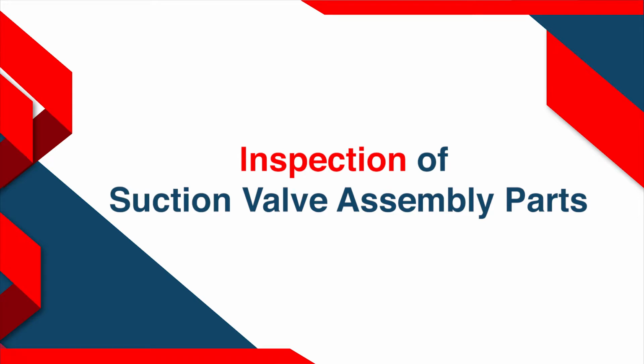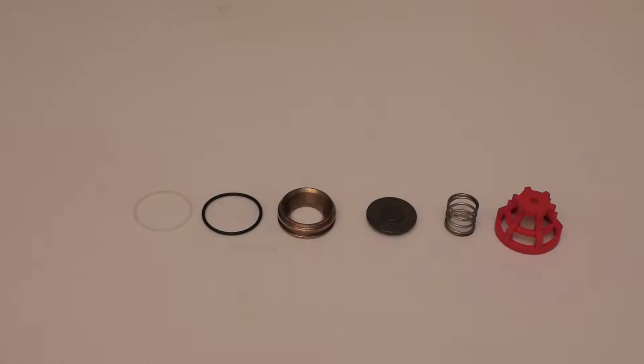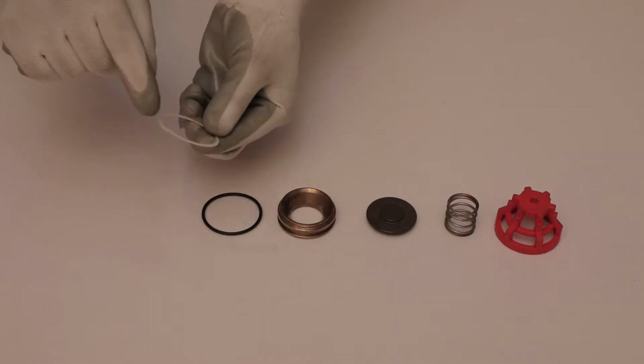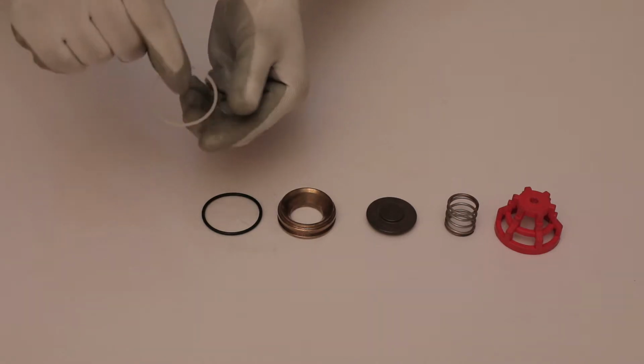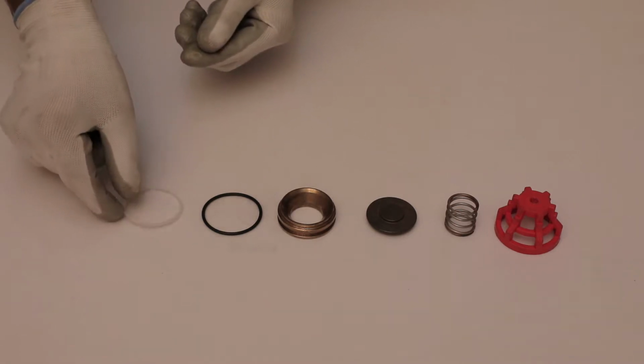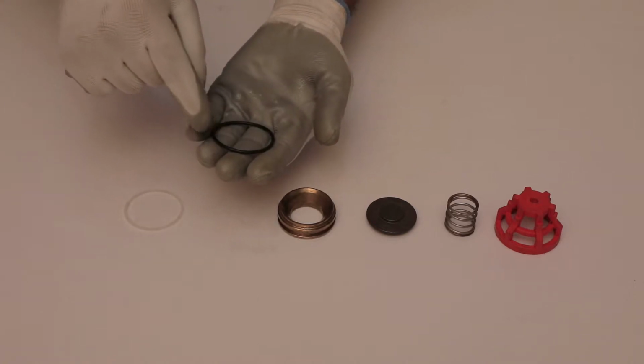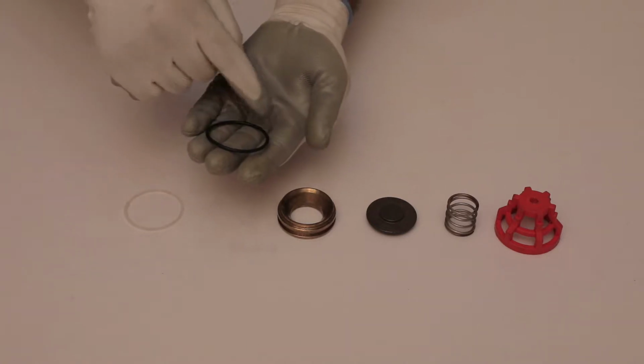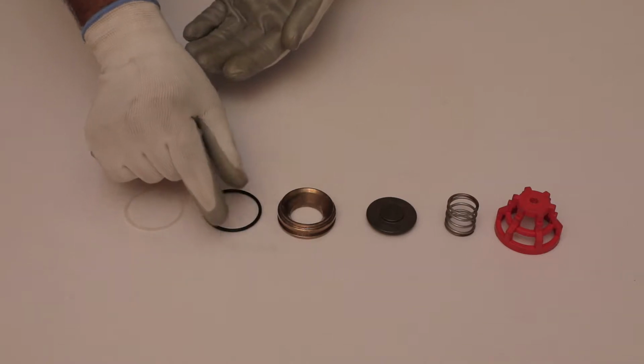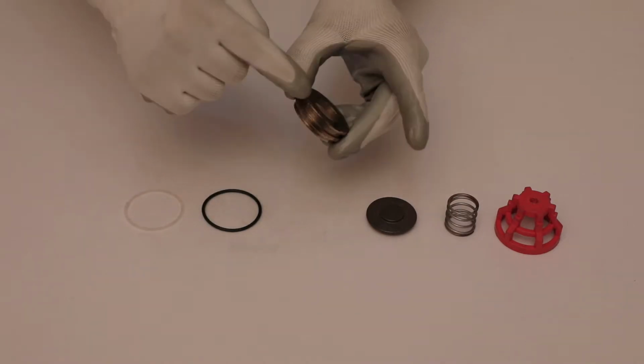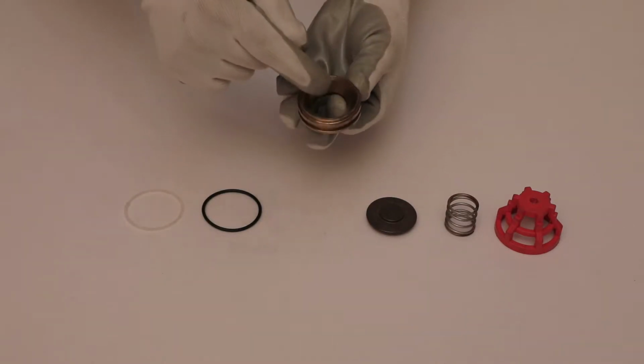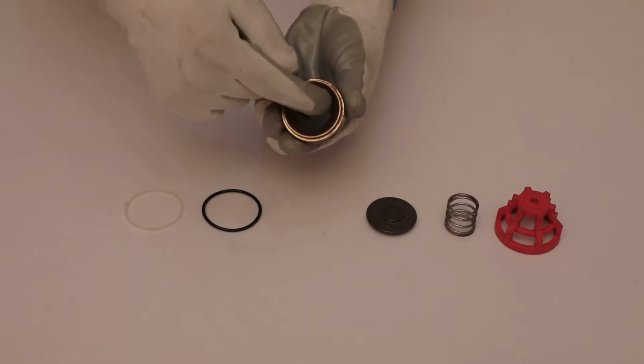Inspection of suction valve assembly parts. Check the backup ring for valve seat for any damage. Check O-ring for any damage. Inspect the surface of the suction and discharge valve seat for any wear or dent mark.